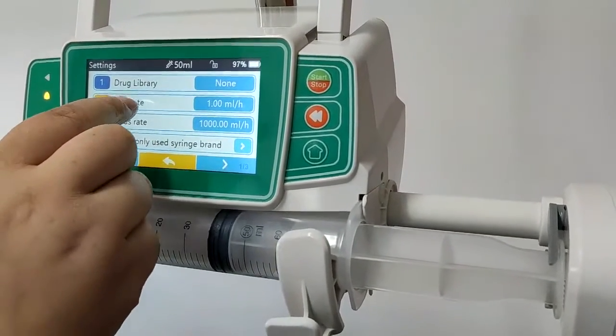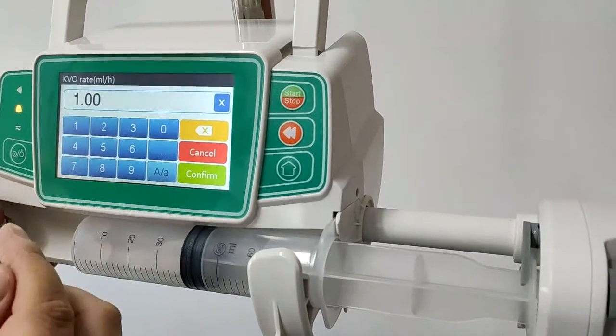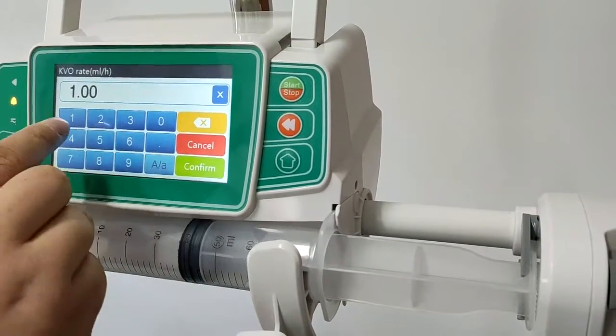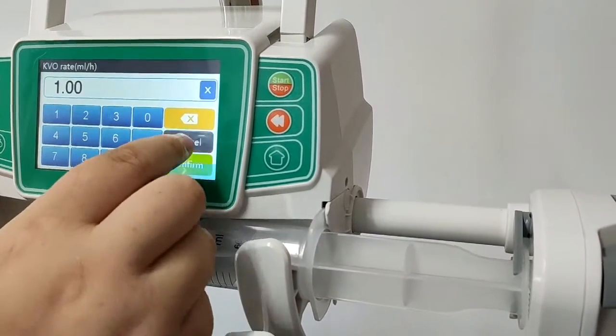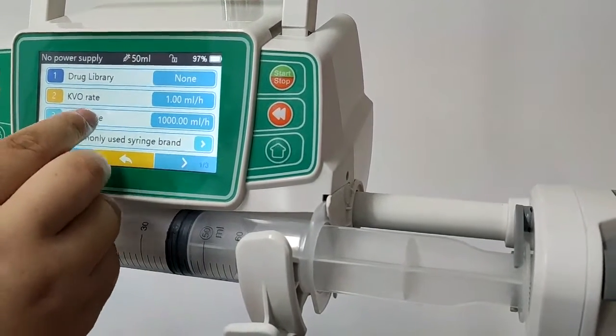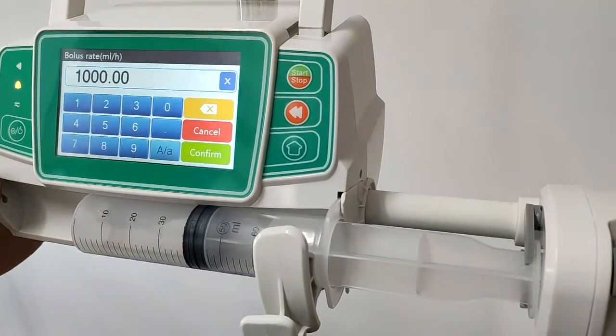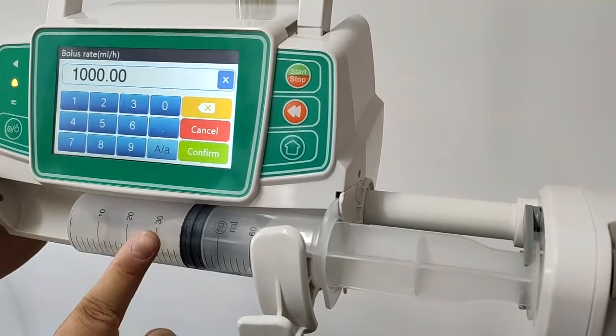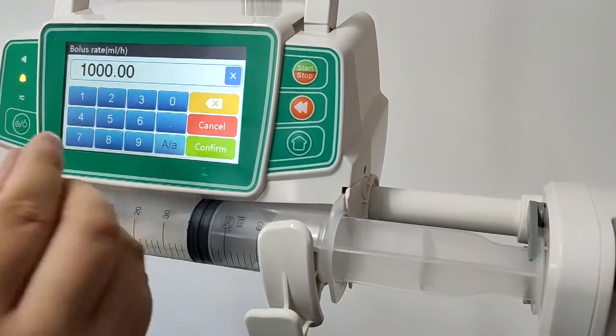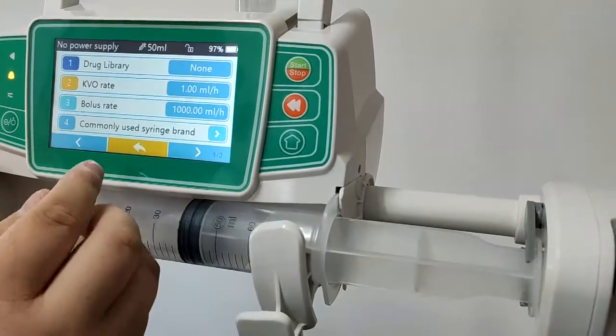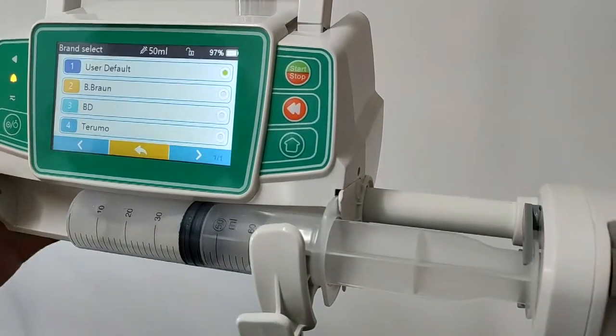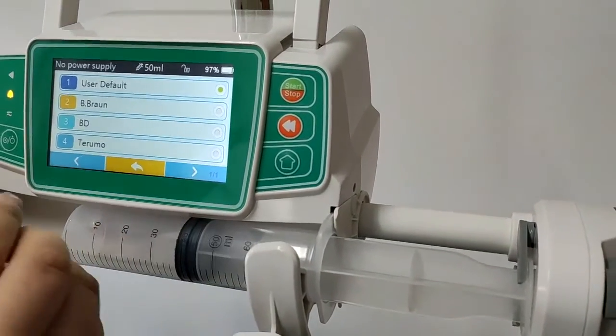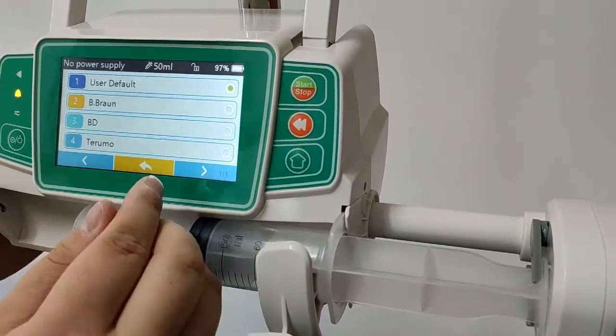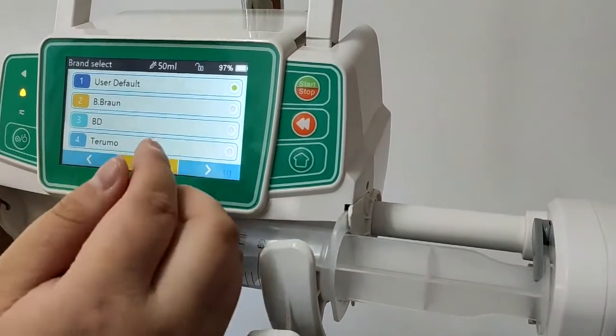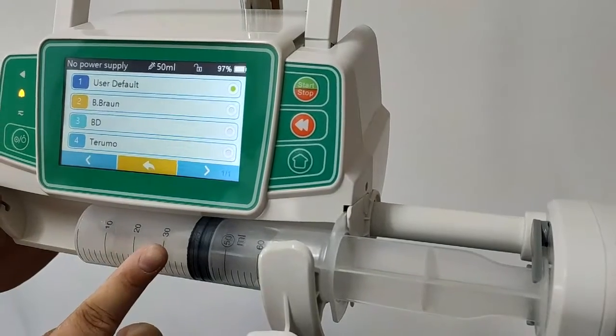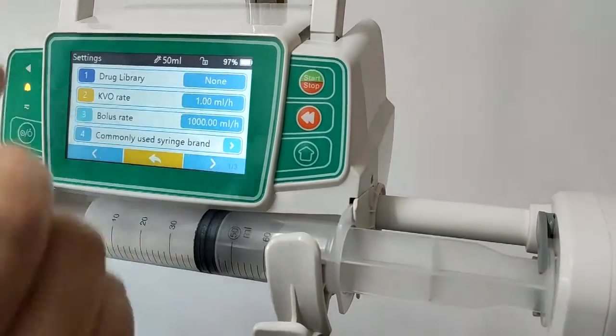And by KVO, you can set the KVO rate from 0.1 to 5 ml. Default one is 1 ml. And by bolus rate, our max rate is 1,500 ml per hour for the 50 ml syringe. If you want to use a lower rate, you can just change. And here, if you have calibrated any brand of syringe into the system, you can choose the brand you want to use. Well, we use the user default one for test, so we choose here.